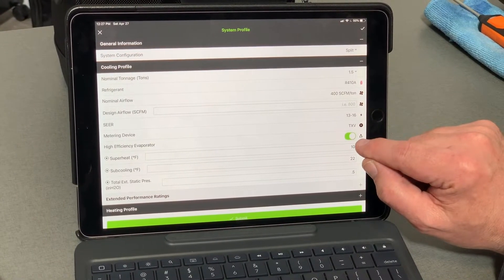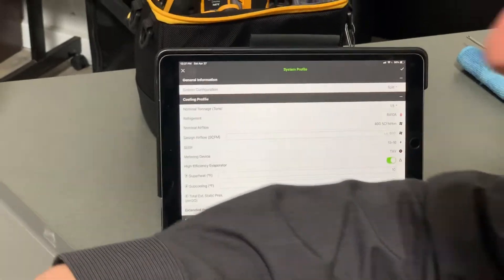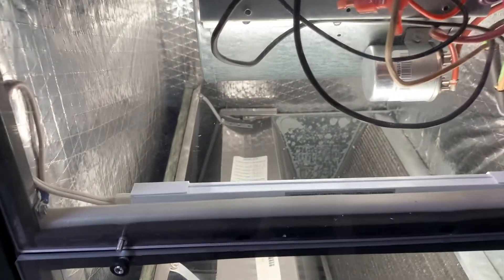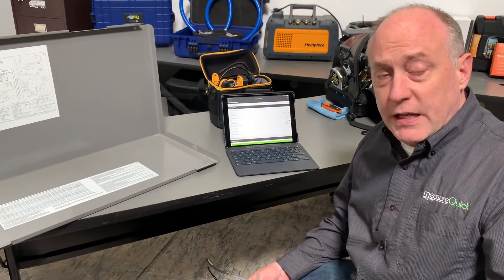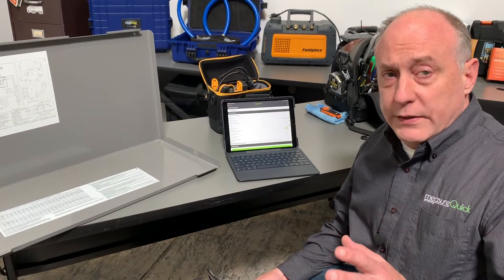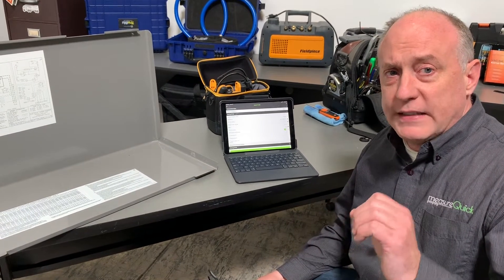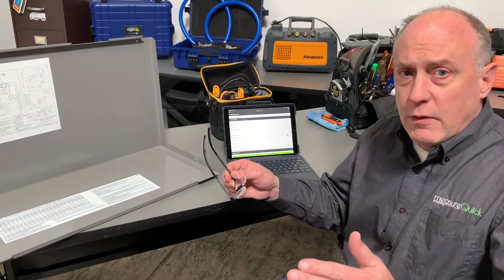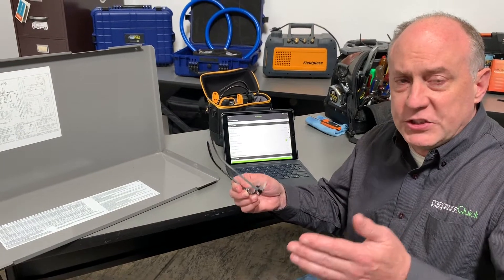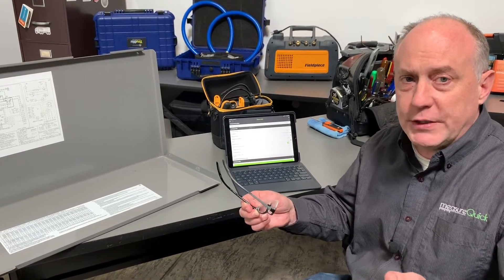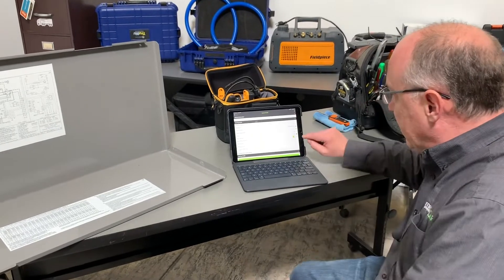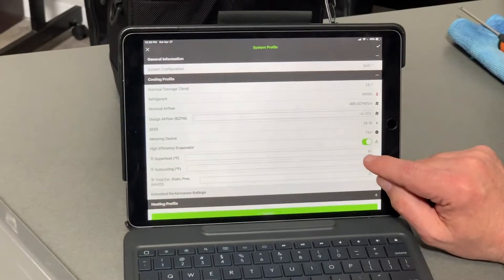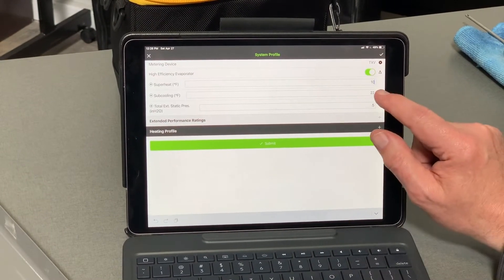Now I need to know whether it's a high efficiency evaporator — this is where it gets a little bit tricky. Looking at the air handler model number, that's a 024, which is a two-ton evaporator. So we have a ton-and-a-half condenser paired with a two-ton coil, which is very common. We call that a high efficiency evaporator. With additional surface area, you raise the boiling point of the refrigerant — the compressor becomes a restricted device, building pressure and operating at a higher evaporator temperature than a typical unit would. So in this case, select high efficiency evaporator. Superheat is typically nominal 10 to 12 degrees.